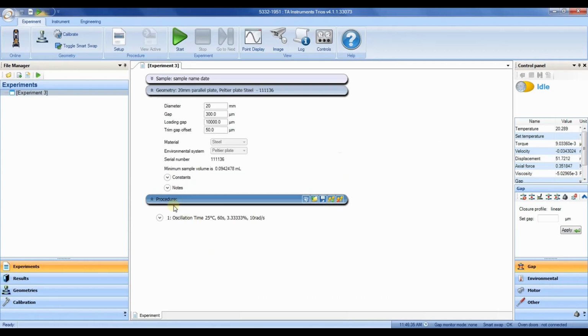The next segment is the geometry. The rheometer automatically identifies the geometry that was installed, which is the 20mm parallel plate Peltier plate steel. The gap is the gap at which you want to do your experiments. And the loading gap is the gap between plates for you to load your sample. Trim gap offset is the difference between your experimental gap and the trim gap. You can get an estimate of volume that is needed to run this experiment. As you can see, it is very small volume.